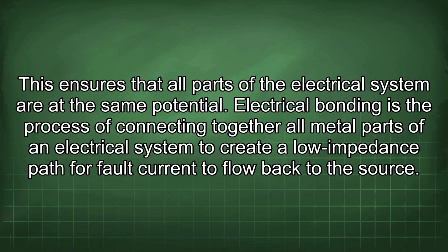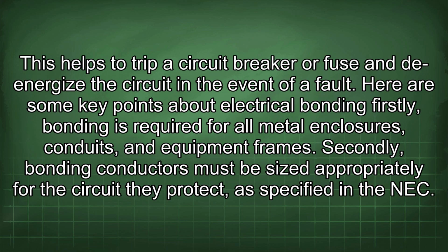Electrical bonding is the process of connecting together all metal parts of an electrical system to create a low impedance path for fault current to flow back to the source. This helps to trip a circuit breaker or fuse and to de-energize the circuit in the event of a fault. Here are some key points about electrical bonding. Firstly, bonding is required for all metal enclosures, conduits, and equipment frames.